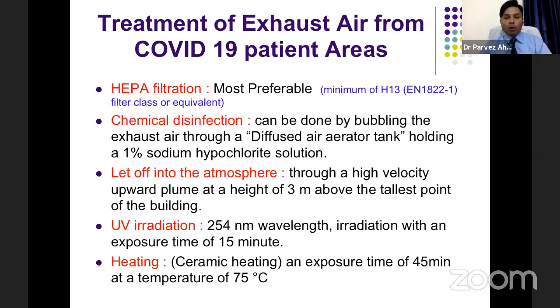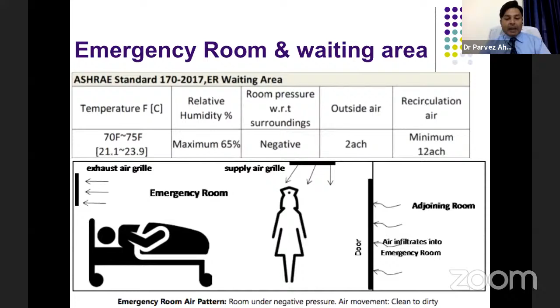This is the emergency room and waiting areas. Generally, the same kind of negative pressure should be maintained, 2 fresh air changes and minimum 12 air changes should be maintained, and air movement should be from clean to dirty areas.